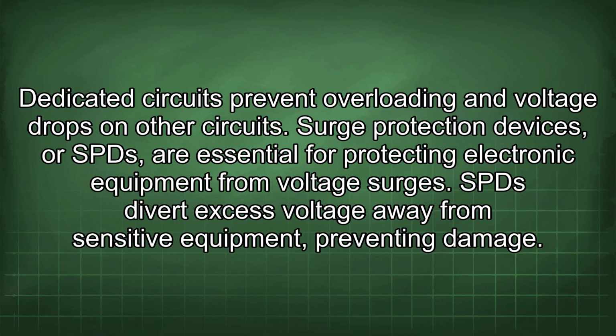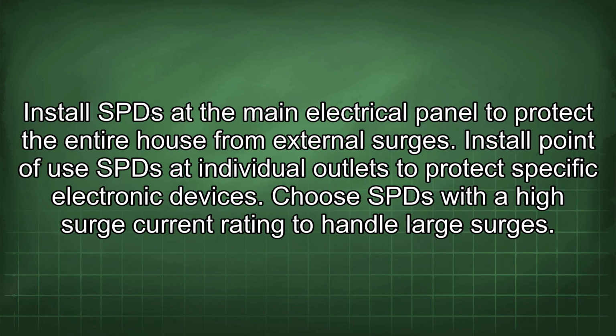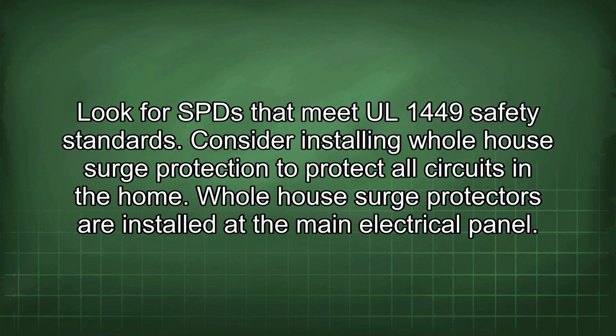Surge protection devices, or SPDs, are essential for protecting electronic equipment from voltage surges. SPDs divert excess voltage away from sensitive equipment, preventing damage. Install SPDs at the main electrical panel to protect the entire house from external surges. Install point-of-use SPDs at individual outlets to protect specific electronic devices. Choose SPDs with a high surge current rating to handle large surges. Look for SPDs that meet UL 1449 safety standards.